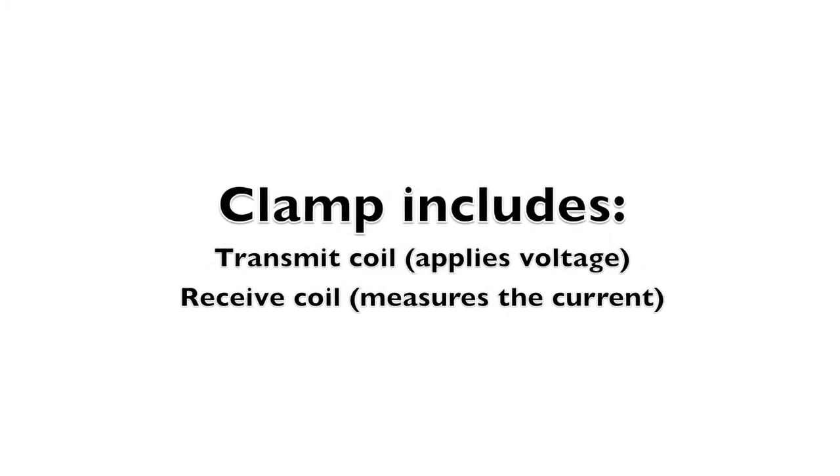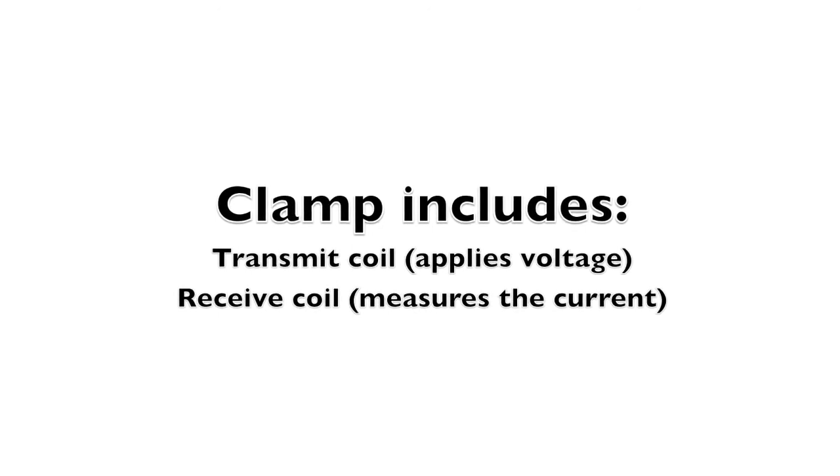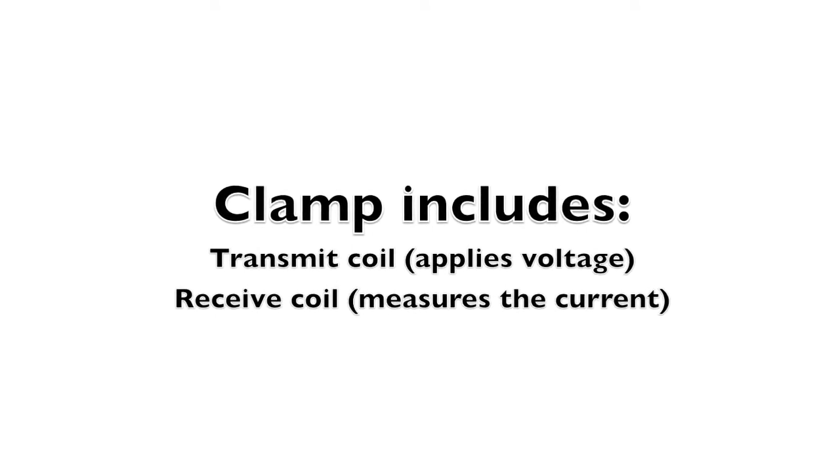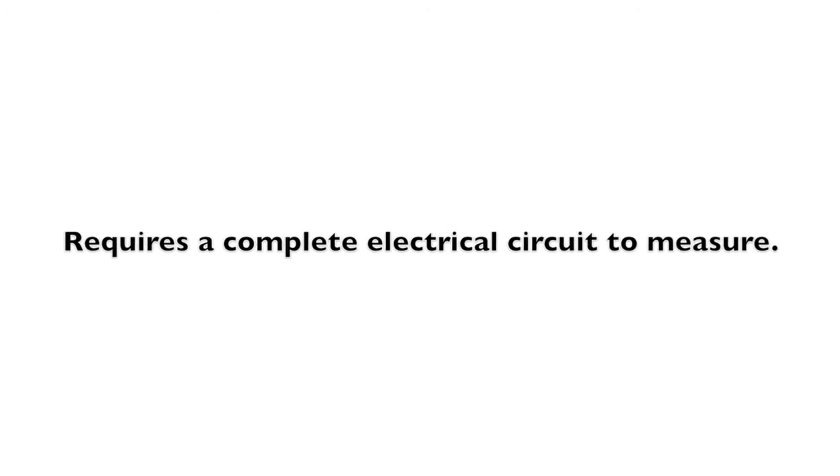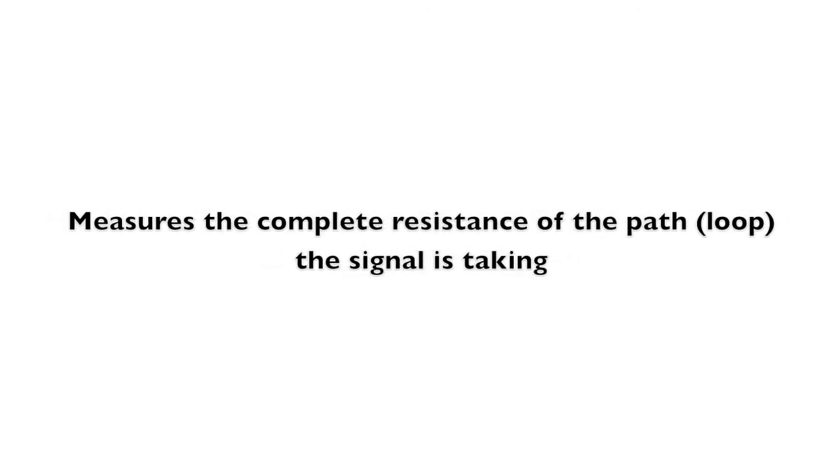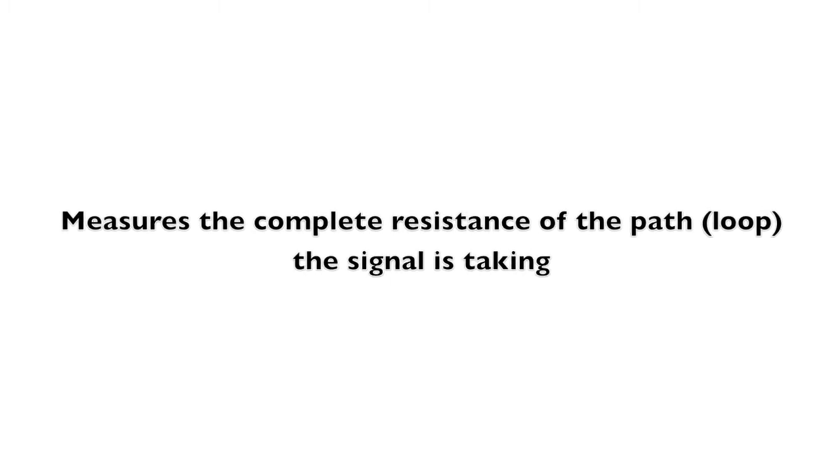The clamp houses two inductive coils, one to establish test current and the other to sense voltage drop. The tester must be able to find a current path back to the jaws in order to make a measurement. With a return path in place, the measurement will be a series loop resistance of the entire current path.